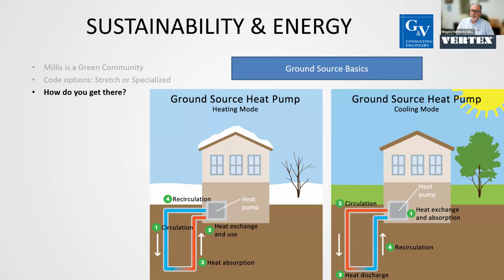That's right. They do run year round, and the pumping energy is pretty substantial because you're talking about moving water through multiple wells for 75 tons of cooling heat. You're talking 10 wells that are 1,000 feet. So you get 10,000 feet, actually 20,000 feet of piping because you're going down and back up across your field into your building. So you have to look at the pumping energy that's involved. And those pumps do run continuously. For a school the size of Millis, they could be 60 horsepower pumps running continuously. So that information also gets built into the life cycle cost to drive you to a certain system. They also have the bleed off because when the wells get too overloaded with either heating or cooling, they also bleed the water off of them to get water replenished from the aquifer.